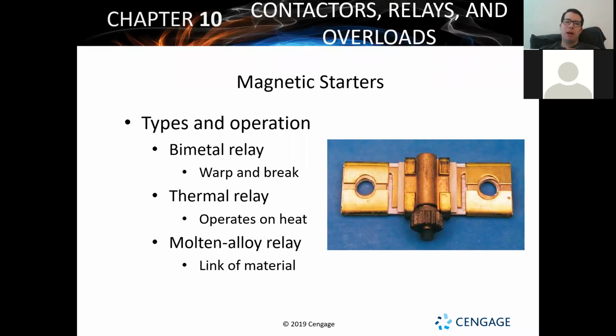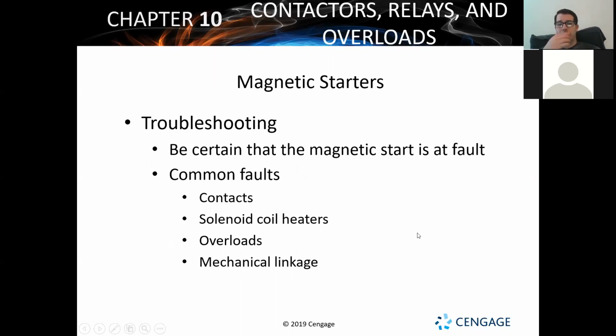So bimetal relay, it's going to be dealing with heat. All right, you've got it where bimetal is always going to be reacting to heat. It's going to bend and warp its shape. Thermal, again, heat. And the molten alloy relay is going to be based on heat as well. Basically, you're going to have it where this molten alloy is going to allow for power to pass through and everything with this link of material. So we've got a couple different styles of them, but again, I'll send that video out later for y'all.